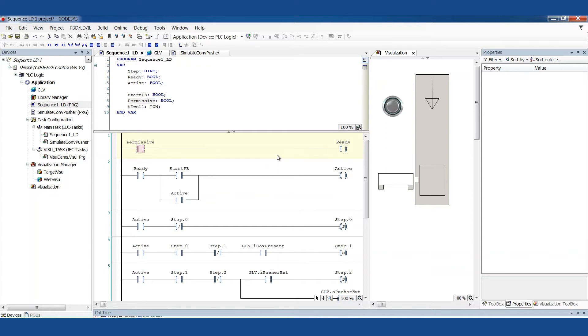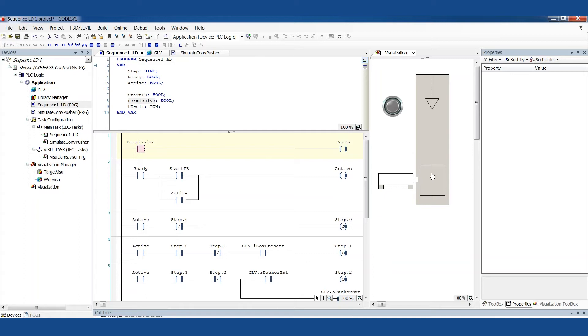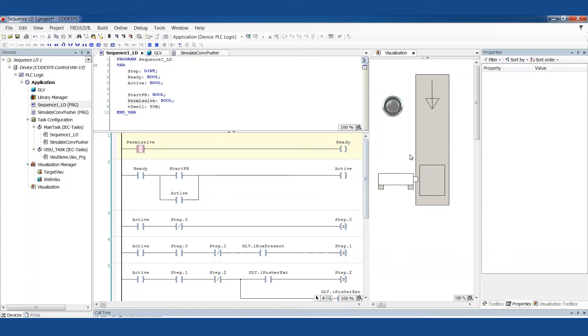I've just got a single permissive bit here. Maybe this is guard doors, e-stops. Maybe it is the system error has to be on, or the system cannot be in a faulted state. Or maybe it has to be in auto mode before the sequence can run. It's nice to have a rung that sums all that up. And then what sets this sequence to start moving? We could actually trigger just on a box showing up. In this case, I chose to have a push button. You obviously never want to start motion without the operator actually telling it to, having some interaction with the machine that's expected to cause motion.